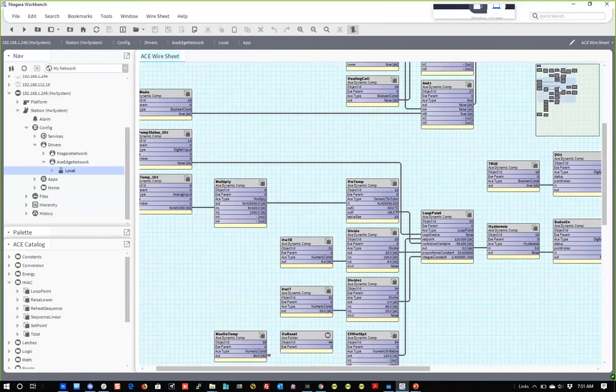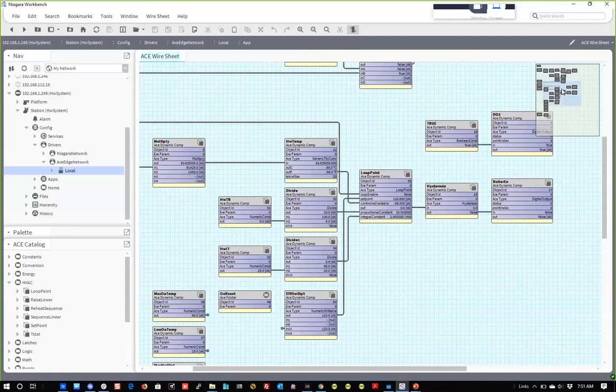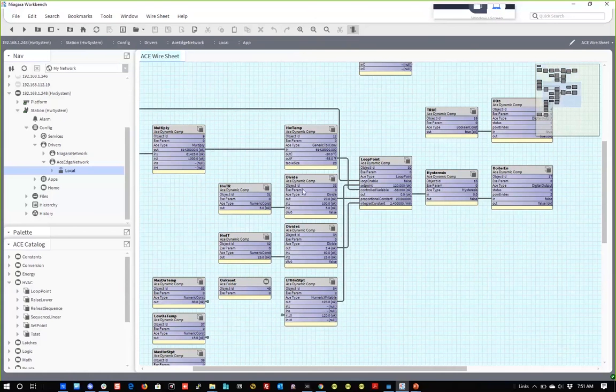If we go down and we look at, yet another programming environment, I still do the same thing on my throttling range and integral time. I do the calculation so the value we enter is what we're used to doing with the Honeywell stuff. It's standard throttling range, standard integral time. Jack, what are those again? 30 and 300? 30 and 300.